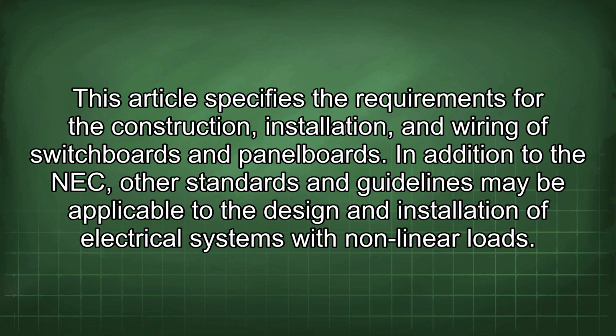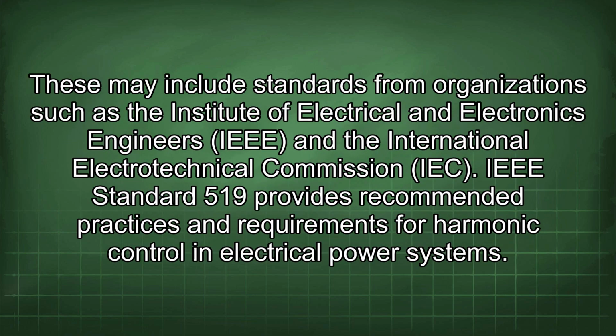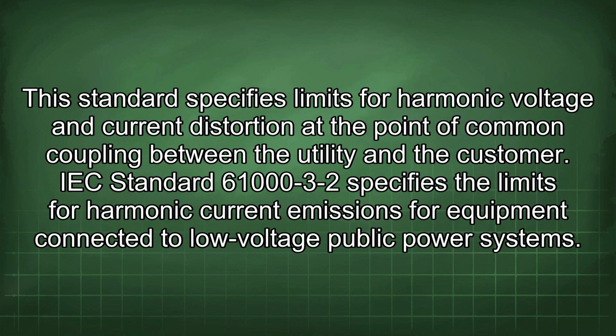In addition to the NEC, other standards and guidelines may be applicable to the design and installation of electrical systems with nonlinear loads. These may include standards from organizations such as the Institute of Electrical and Electronics Engineers, IEEE, and the International Electrotechnical Commission, IEC. IEEE Standard 519 provides recommended practices and requirements for harmonic control in electrical power systems. This standard specifies limits for harmonic voltage and current distortion at the point of common coupling between the utility and the customer.